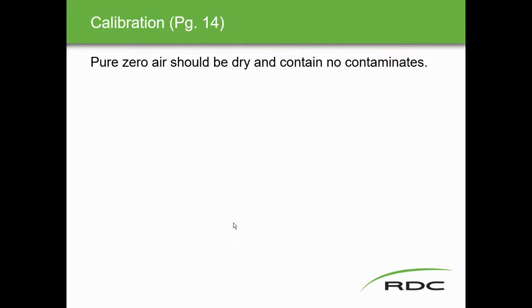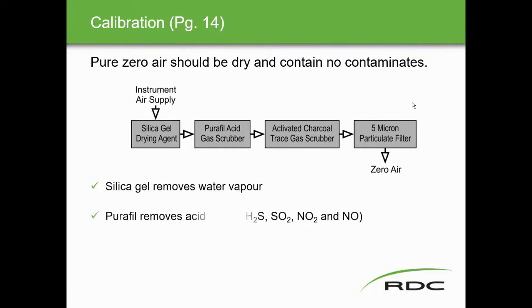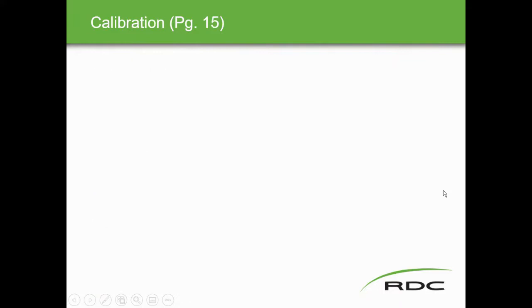For calibration, zero air must be dry and contain no contaminants. The zero air supply passes through: a silica gel drying agent to remove water vapor; a Purafil acid gas scrubber to remove H2S, SO2, NO2, and NO; an activated charcoal scrubber to remove trace gases; and a five-micron particulate filter. This ensures the zero air is pure enough for parts-per-billion level chemiluminescence measurements.